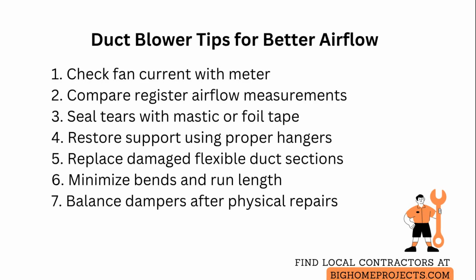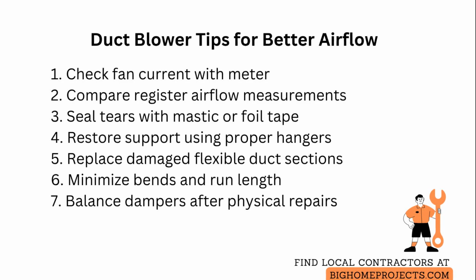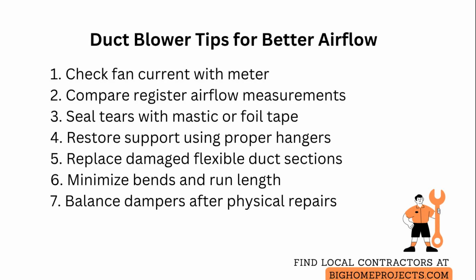Always balance dampers only after physical repairs so the blower is not compensating for distribution defects, and document before and after measurements to confirm motor load and airflow return to expected values.